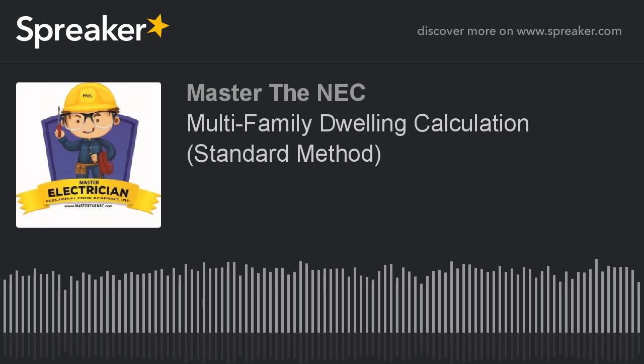You might have 4 or more appliances, and you can apply a 75% demand factor to them. Well, in this case, since we have 18 units but only one appliance, which is the water heater, we can still apply it as more than 4. So in that case, we're going to use a 75% demand factor because we're allowed to do that, and that's allowed in 220.53.